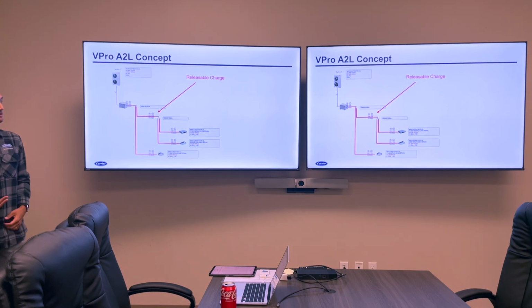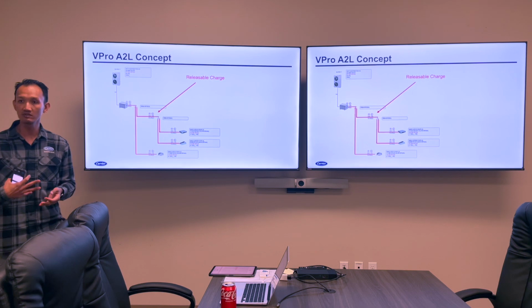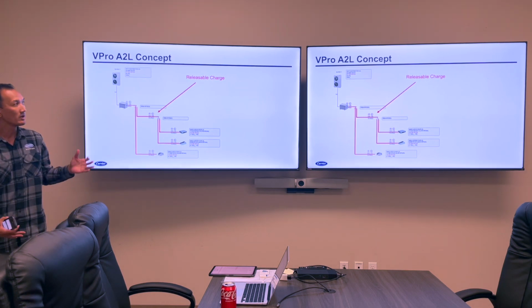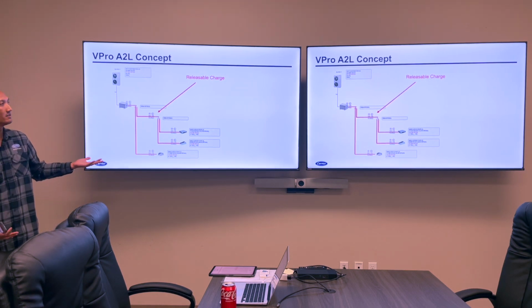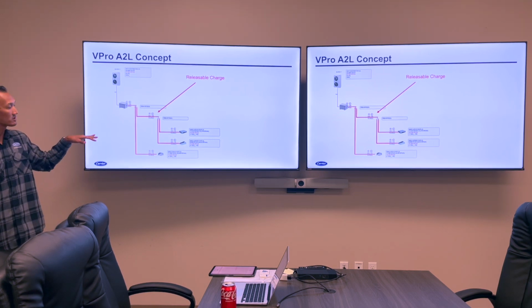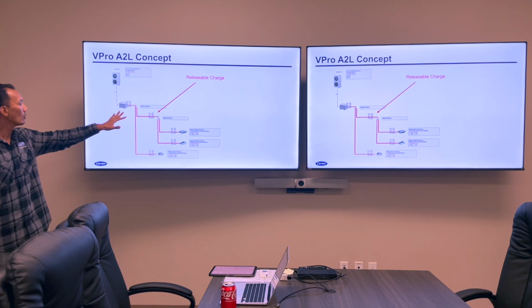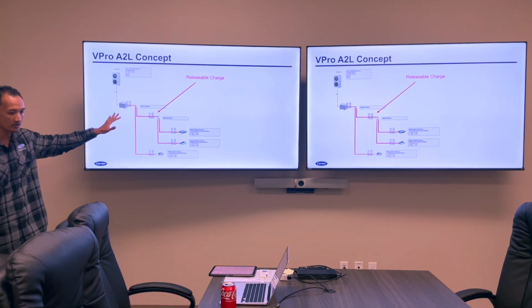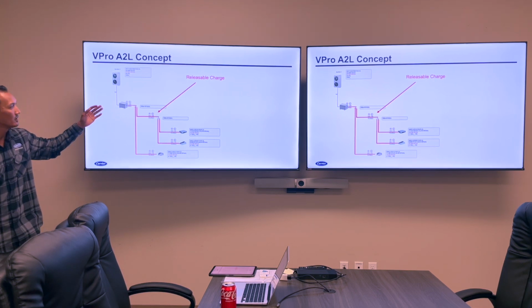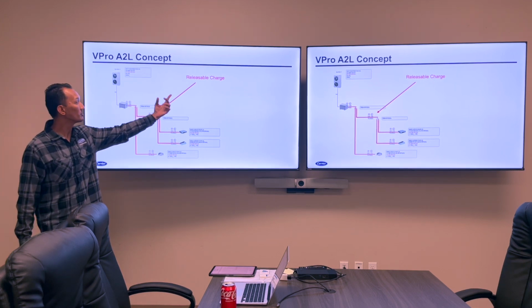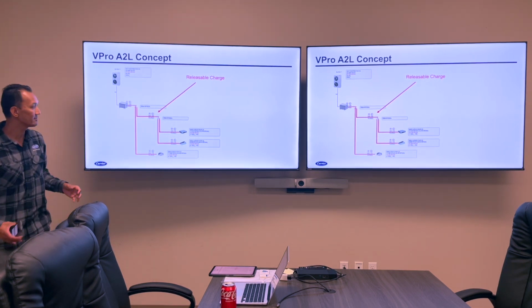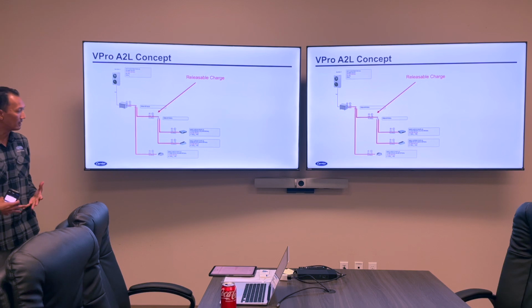we're not going to always have simple systems like that. If we do need to introduce an SV box, we have software that helps us calculate and lay this out for you. So our software is called VPro. If you have an application where you do have an SV box, our software will actually help us calculate the releasable charge, which is the number that we need to figure out to make sure this complies with local code or ASHRAE.